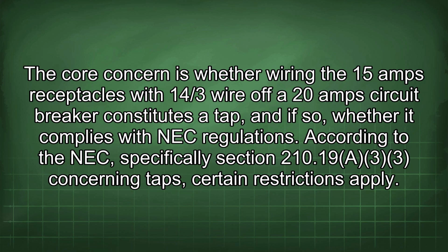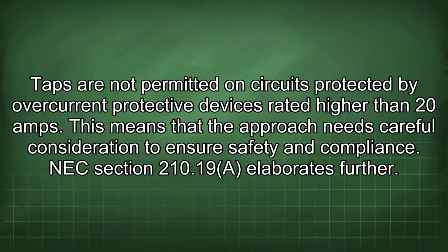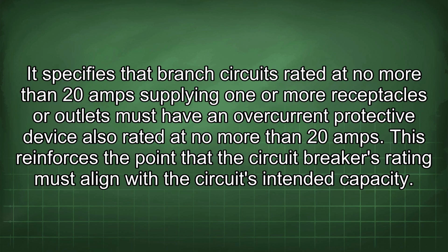According to the NEC, specifically section 210.19(A)(3)(3) concerning taps, certain restrictions apply. Taps are not permitted on circuits protected by overcurrent protective devices rated higher than 20 amps. This means that the approach needs careful consideration to ensure safety and compliance. NEC section 210.19 elaborates further. It specifies that branch circuits rated at no more than 20 amps supplying one or more receptacles or outlets must have an overcurrent protective device also rated at no more than 20 amps. This reinforces the point that the circuit breaker's rating must align with the circuit's intended capacity.